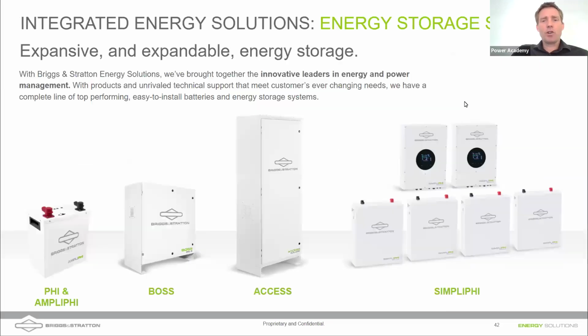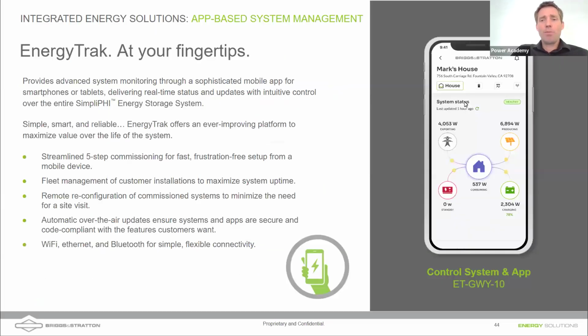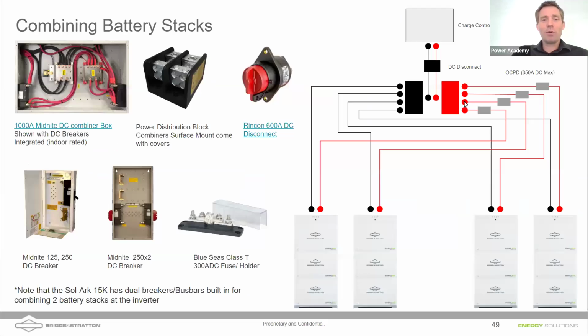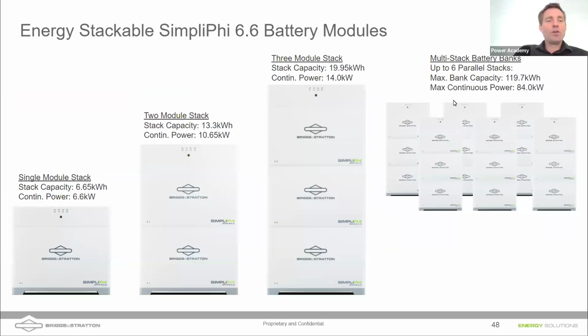I talked about the charging and discharging range before—jumping ahead to this new 6.6 battery, 6.65 kilowatt hours. Overall, a single battery is capable of a 1C discharge rate, meaning a 6.65 kilowatt hour battery can do 6.6 kilowatts of output, which is a large power output. A 2-module stack can do over 10 kilowatts of power output, and these come in a fairly small format.